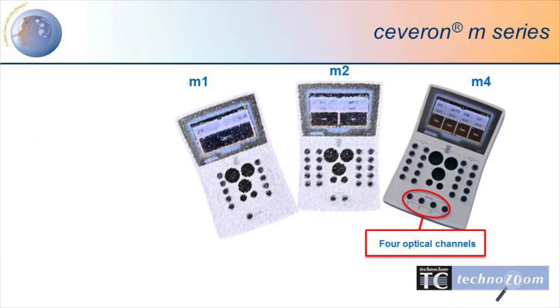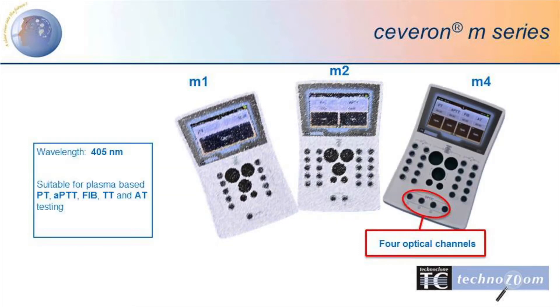The Ceveron M4 uses the same wavelength as the M2 but has four channels and is capable of testing four samples at the same time.